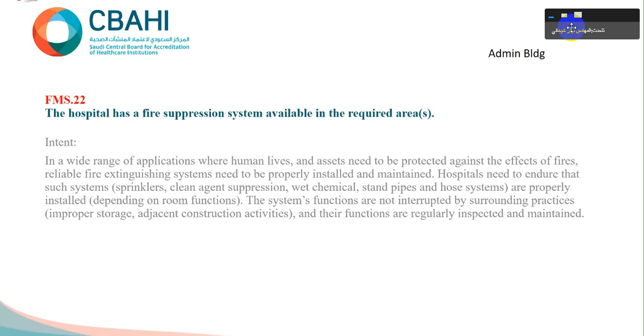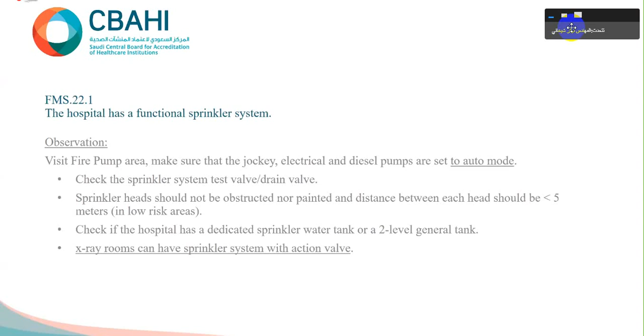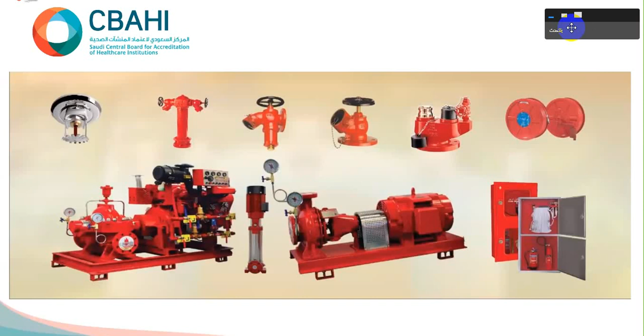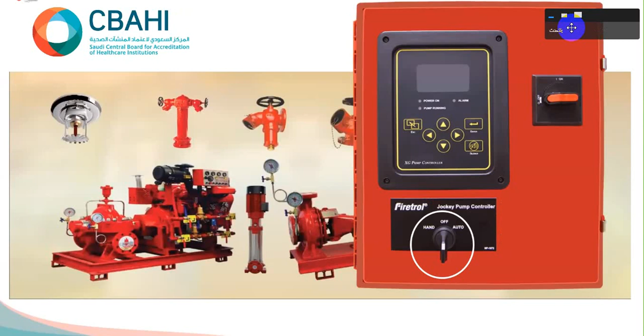Observation, to make sure that we have a functional sprinkler system, we usually visit the fire pump to make sure that the jockey pump is working. We ask the technician to open the drain. If the jockey pump starts, it means our system is good. Then we can try the fire hose reel to evaluate the pressure, whether it's good or not. And please be sure that the electrical and diesel pumps in the pump room are set to auto, because most of the technicians usually leave the pump on off mode, which is not acceptable at all. Should be auto all the time.